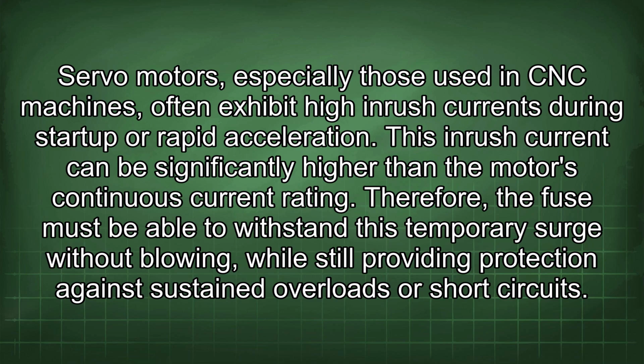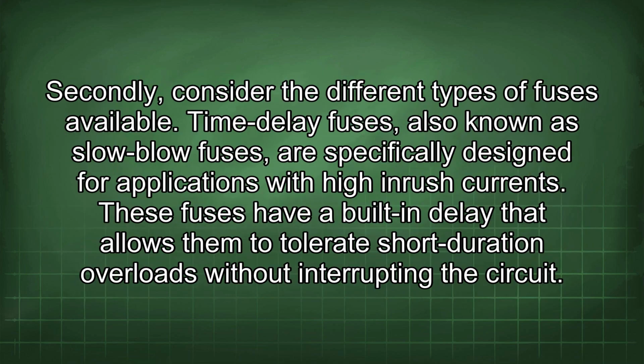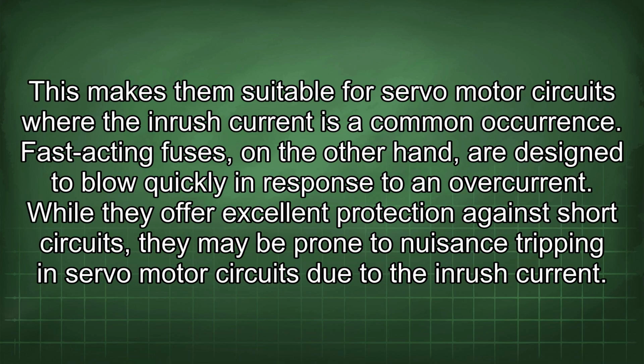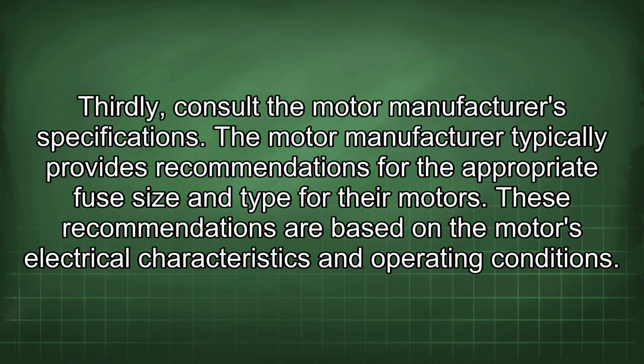Secondly, consider the different types of fuses available. Time delay fuses, also known as slow blow fuses, are specifically designed for applications with high inrush currents. These fuses have a built-in delay that allows them to tolerate short duration overloads without interrupting the circuit. This makes them suitable for servo motor circuits where the inrush current is a common occurrence. Fast-acting fuses, on the other hand, are designed to blow quickly in response to an overcurrent. While they offer excellent protection against short circuits, they may be prone to nuisance tripping in servo motor circuits due to the inrush current. Thirdly, consult the motor manufacturer's specifications.